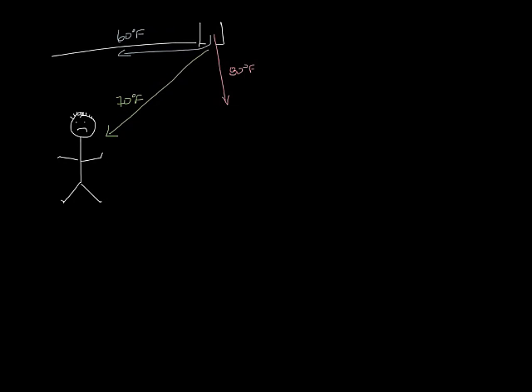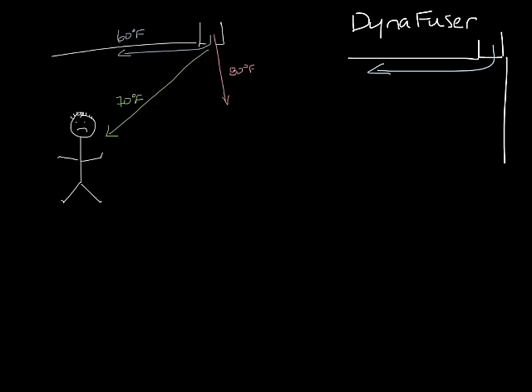The bimetal alloy that the DynaFuser uses snaps between the heating and cooling positions. So if the supply air temperature is 55 degrees, the unit will snap to the cooling position and stay there until it sees 82 degrees. Then it'll snap to the heating position and stay there until the supply air drops below 62 degrees again. So why is this two-position actuation important?